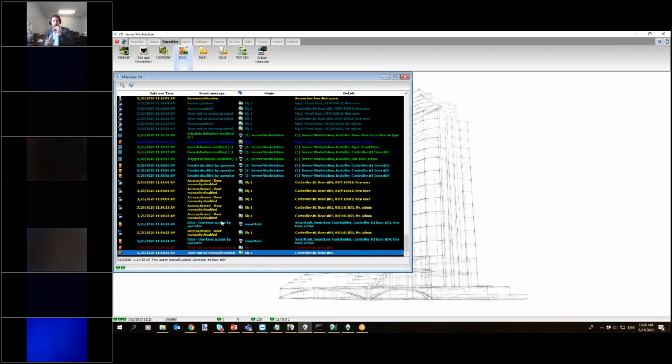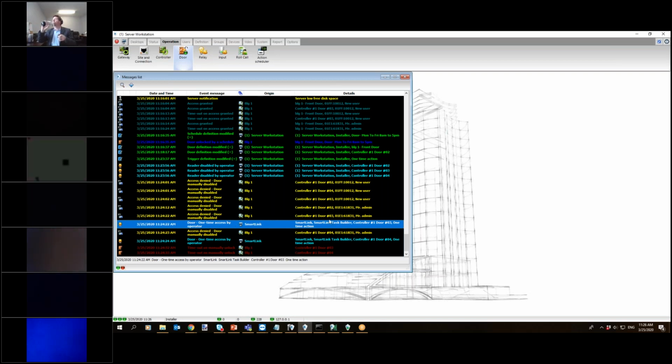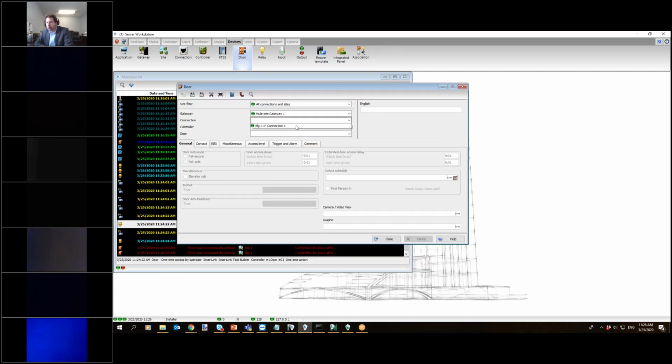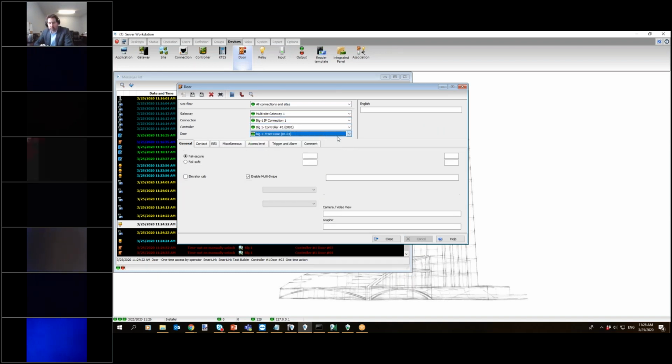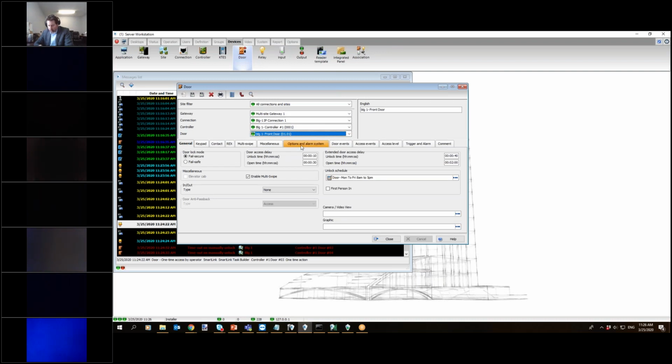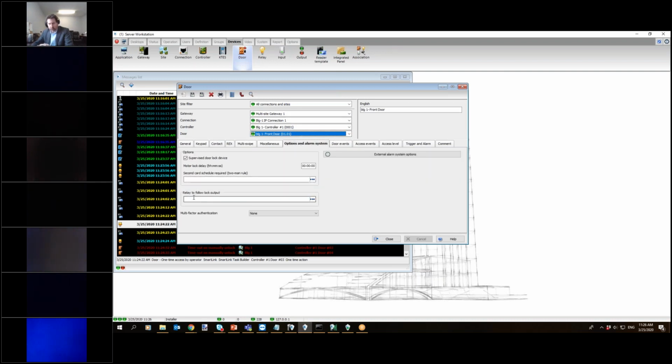And lastly, this applies on the lock output. This will unlock the door. So if I go to my doors, certain people here, when they program their lock outputs, they wire the door, the strike on the lock output, which is perfect. Also, they wire the user relay for the lock output, which is relay to follow lock output. That's perfect.